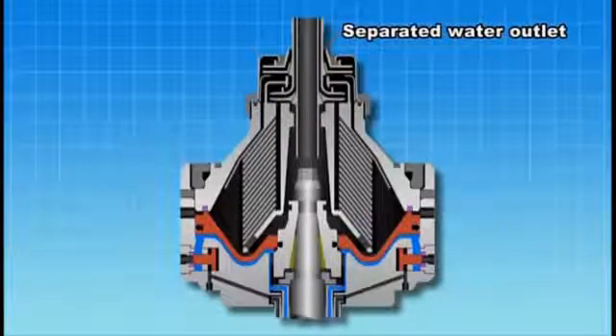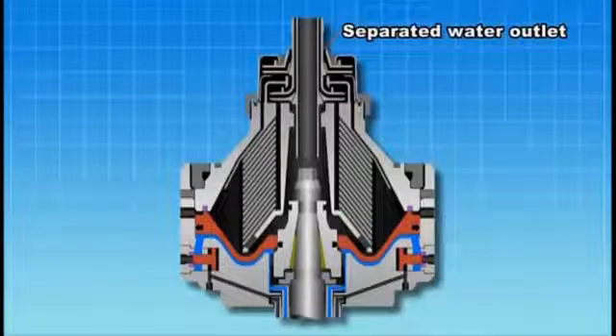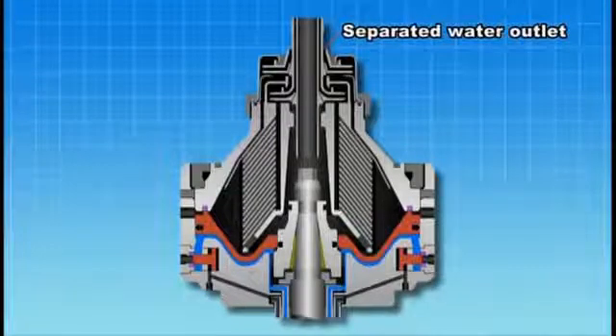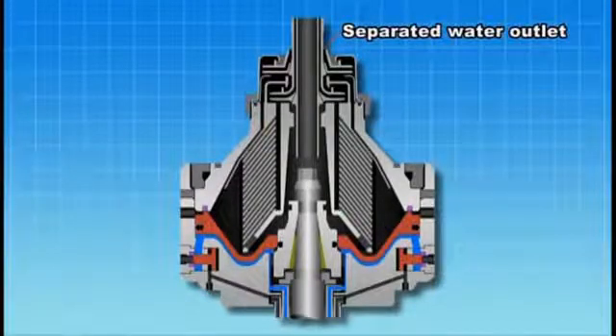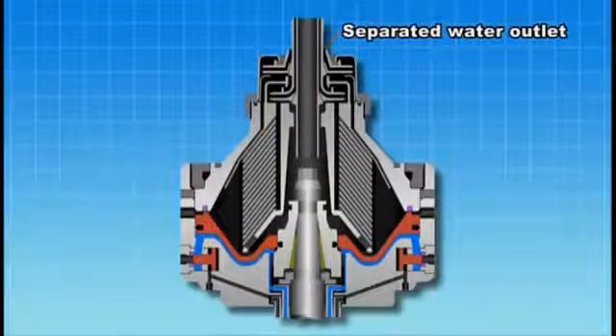Prior to passing oil through the purifier, sealing water must be provided to ensure that oil does not flow out to the separated water outlet.